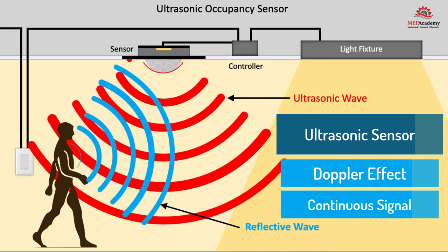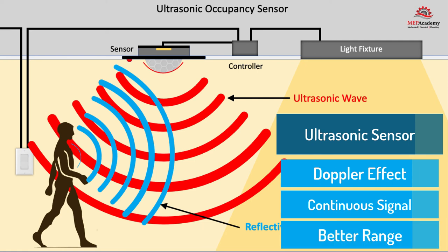This will require the ultrasonic sensor to most likely be hardwired to provide the constant energy for operation. Ultrasonic sensors are good at detecting movement that may occur behind a partition or bookcase, which isn't in the direct line of sight of the sensor. This technology will pick up slight movements of an occupant sitting at their desk reading a book or typing on their computer. The ultrasonic occupancy sensor also has a greater detection range than passive infrared sensors.